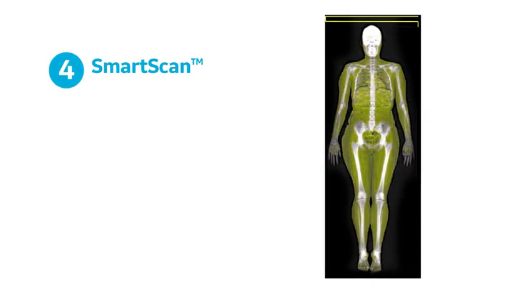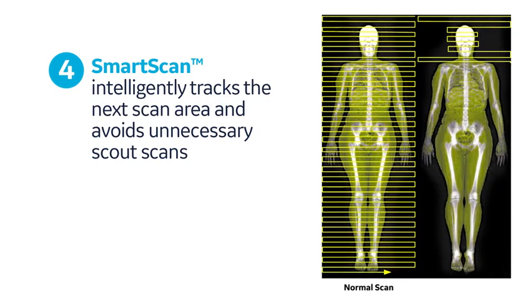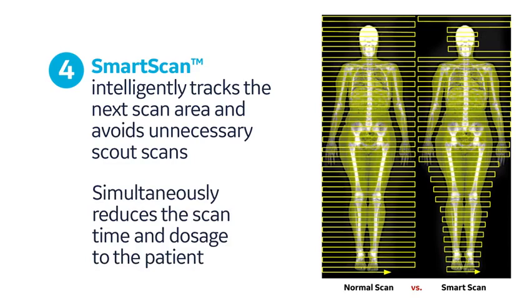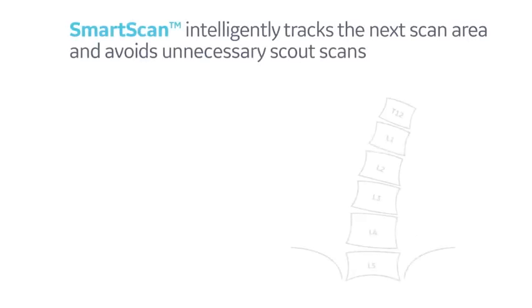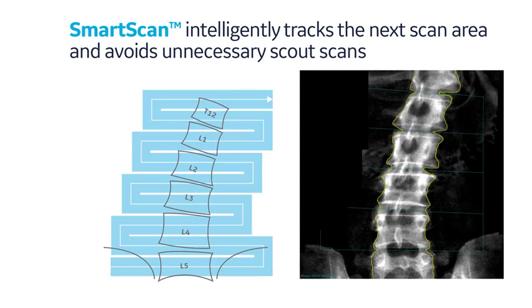Smart scan is an exclusive feature in DEXA bone densitometers from GE Healthcare, which performs transverse scanning of the bone using the narrow fan beam scan. Bone regions are identified after each transverse sweep and used to estimate where to begin exposing the patient to X-rays on the subsequent sweep. Smart scan simultaneously reduces scan time and dosage to the patient. For example, since smart scan follows bone, it can track and capture a scoliotic spine without requiring a scout scan, in comparison to the overarching sweep characteristic of wide fan beam systems.